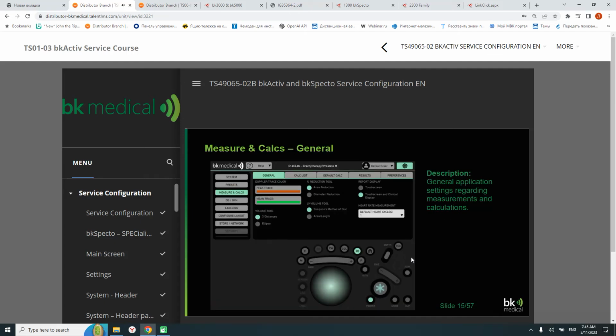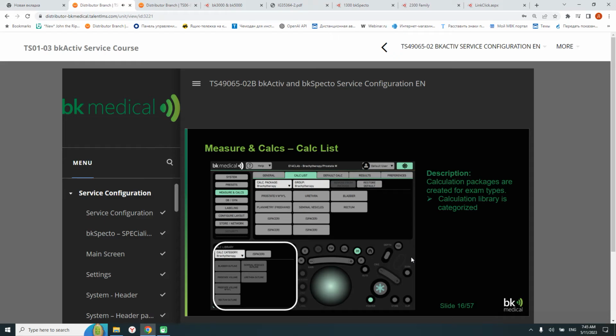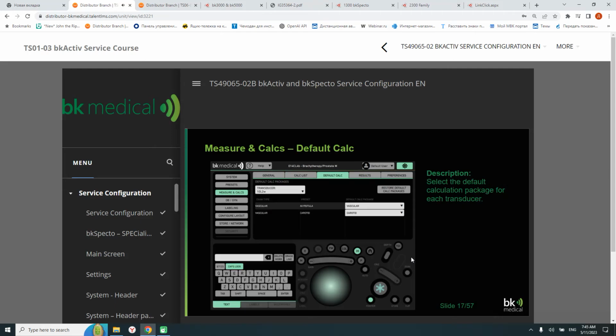The next category is Measure and Calcs. This is mainly application-related settings regarding calculations and measurements. The Calc List tab is where the Calc List categories are defined. A Calc category is a list of calculations related to a specific exam type. The library of calculations can be used to customize the content in the calculation package. In the Default Calc tab, it is possible to select which calc package is default for all presets assigned to each transducer.